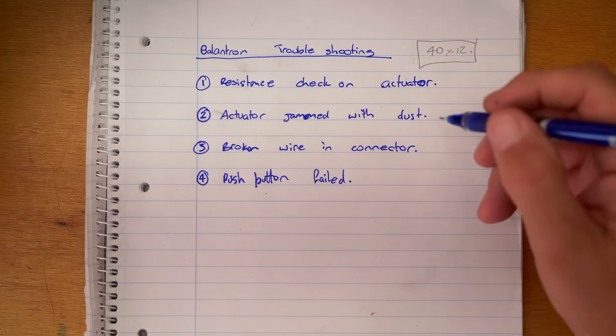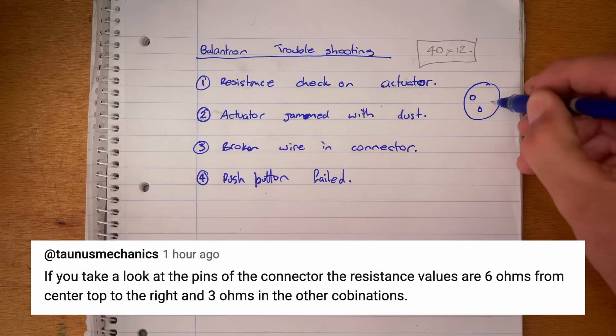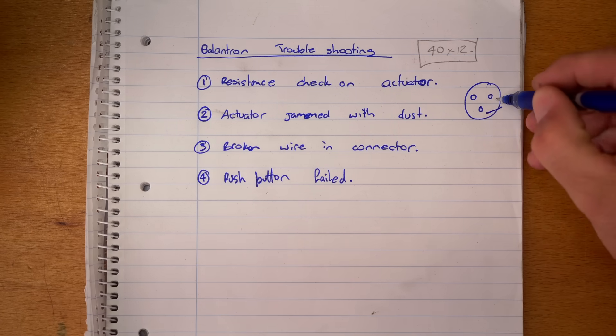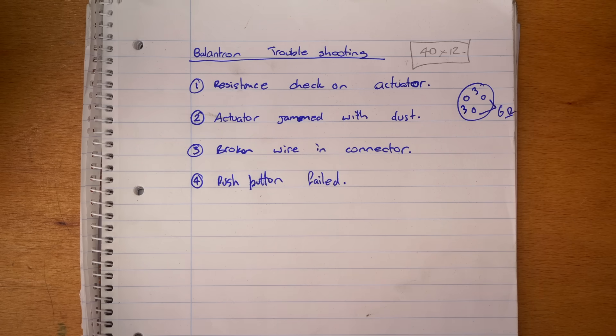Now one really excellent input was from Taunus Mechanics who pointed out that on that connector I should have six ohms between these two and then three and three in the other combinations.